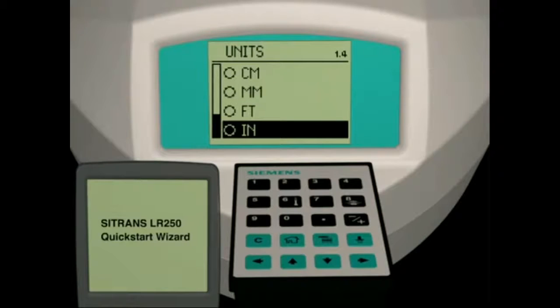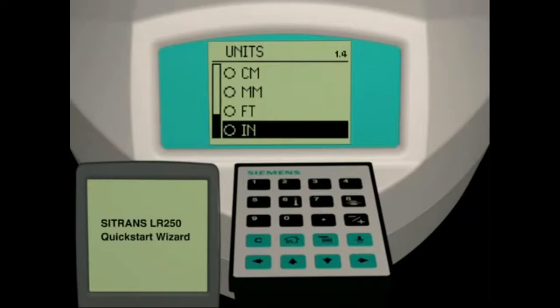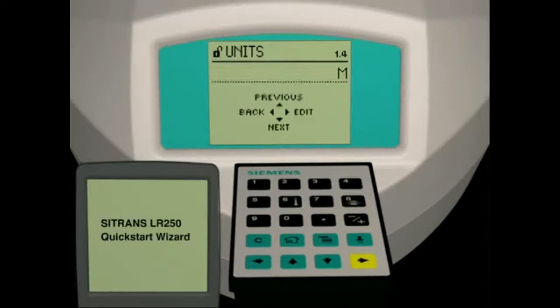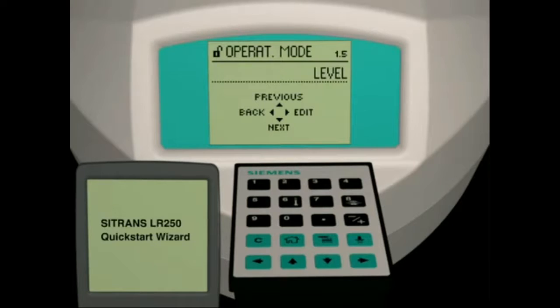The unit of measure selection defines the units displayed when the LR250 is in run mode and the unit of measurement used for our high calibration point and low calibration point. Our application will use meters. Press the right arrow key to set this parameter, then press the down arrow key to move to the next parameter.